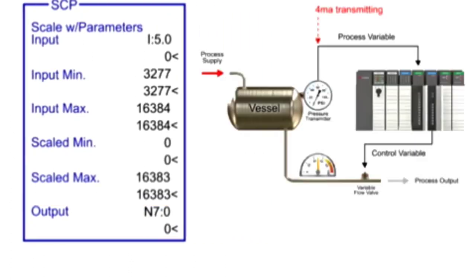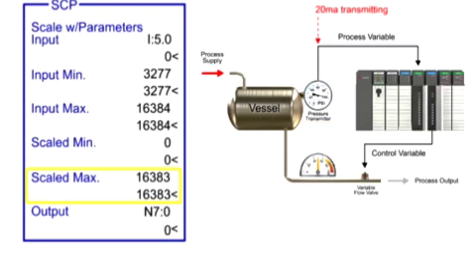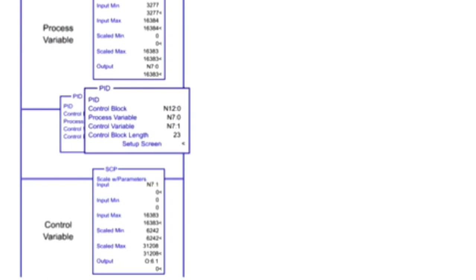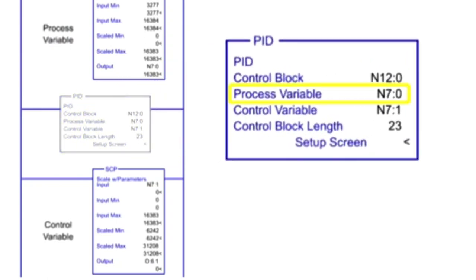For example, when the minimum pressure of 0 PSI is measured, a scaled value of 0 is transferred to the SCP output, and when 100 PSI is measured, a scaled value of 16,383 is transferred to the SCP output. In the PID instruction, the process variable parameter is programmed as an integer file, which is the scaled value from the SCP instruction.